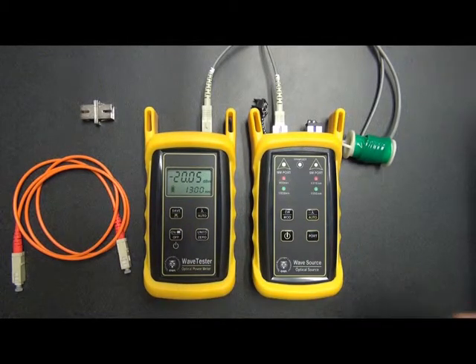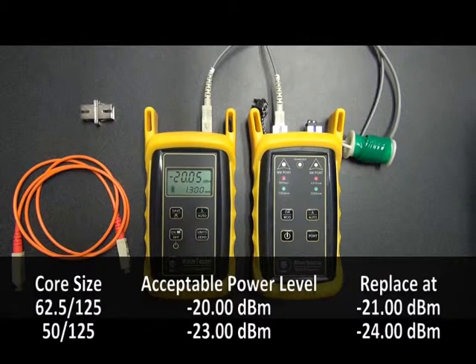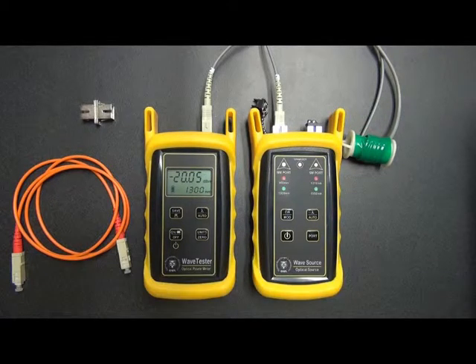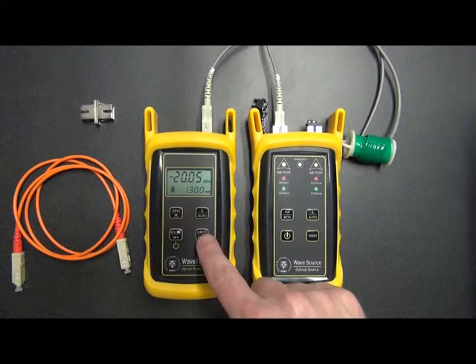Okay, again, we want to see a power level that's around minus 20. In this case, it's just a very little bit below minus 20. So this also confirms that this reference cable is good for use, and it also confirms that the WaveSource is in proper calibration. Again, we can zero out this wavelength.